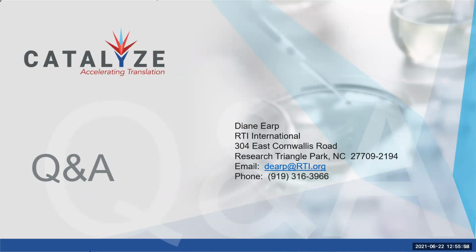Just to support what Mike has just said, this goes back to the presentation. What I was suggesting to you is understanding the risk profile, the significant or non-significant risks, and which classification the device will fit in is really important, not only for your funding process, but the timelines of development. And it shows that you've thought this part through. If you haven't had a conversation with the FDA, you've identified your predicate device, it fits nicely together, and you feel pretty strongly that you have a good, strong defendable position, I think putting that into your submission, along with a timeline for when you feel you'll have enough data to talk to the FDA, is a good strategy.